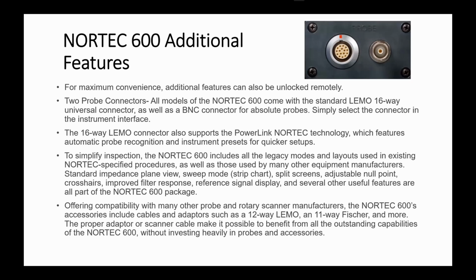Additional features on the 600. Again, we can unlock those features remotely, upgrading the unit. It comes with 2 probe connectors. All the Nortec 600s come with the standard LEMO 16-way universal connector, as well as a BNC connector for those absolute probes. All you've got to do is simply select the connector in the instrument interface and hook up to it.